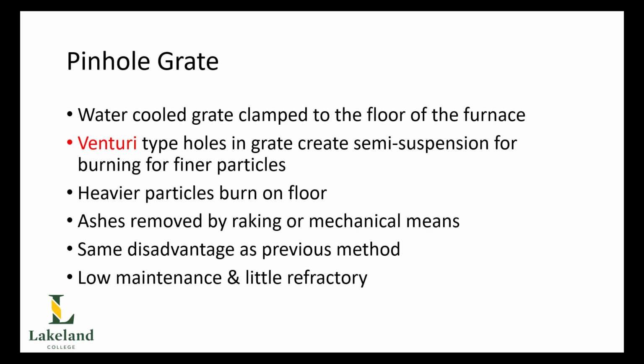Okay, the next one to talk about is a pinhole grate. A pinhole grate is basically a water-cooled grate that is clamped to the floor of the furnace, and it uses yet another application for our Venturi principle. Now, you should remember the Venturi principle: it's basically a constriction within a pipe that causes an increase in velocity that causes a reduction in pressure. That's the whole idea of Venturi with an application of Bernoulli's theorem.